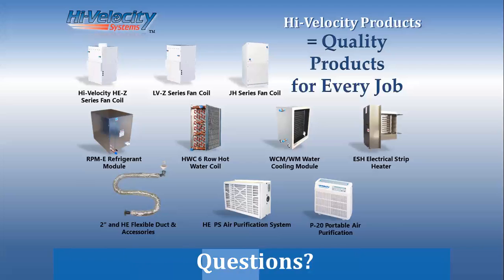When you spray foam a home 100%, not only does it become 100% sealed, but your load requirements drop dramatically. And how do you find a system that's only going to produce 17,000 BTUs of heating, 1 ton of cooling, but still meet the ventilation requirement of the home just to keep it fresh and the CO2 level to an economical level? Well, there's a fine line between that, installing a ducted air system and keeping the loads low as well. Spray foam is a great technology on making tighter, more efficient homes, but it creates these low load mechanical issues, of which we feel like we have a great solution for that.